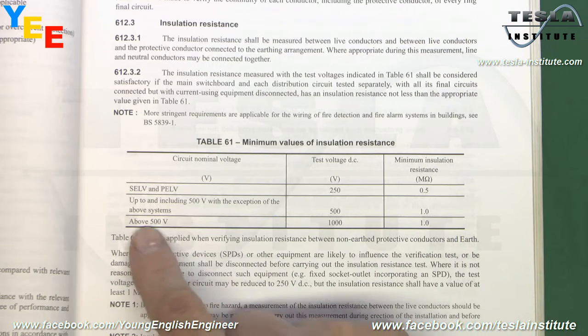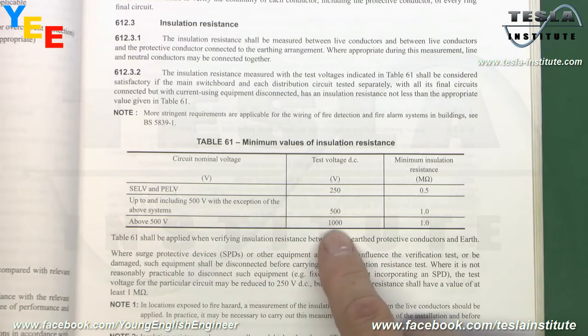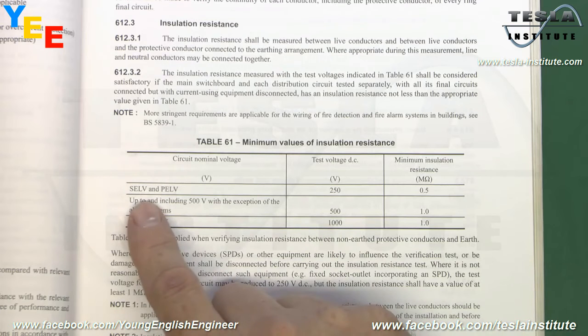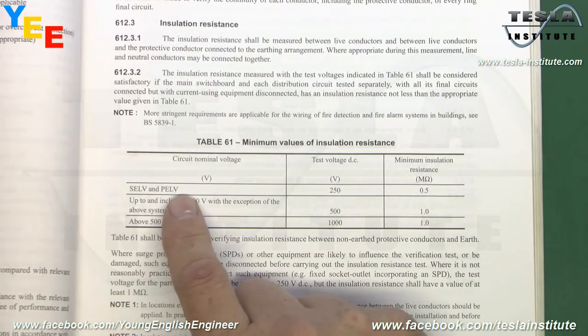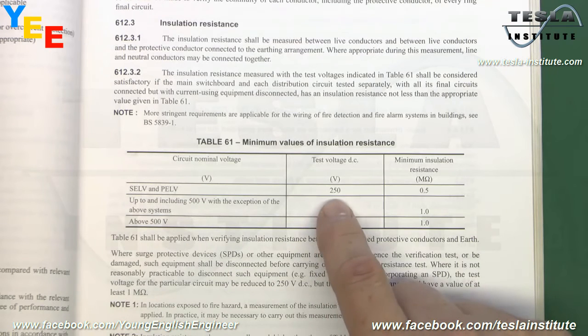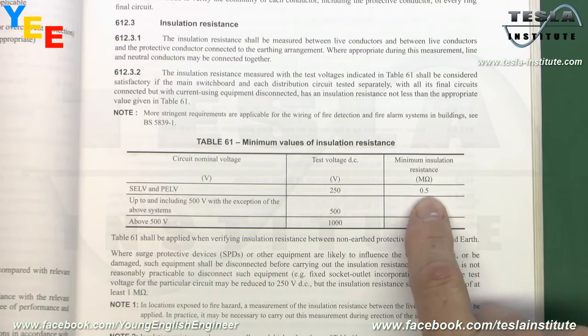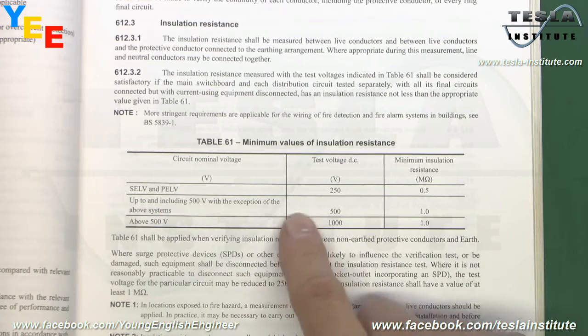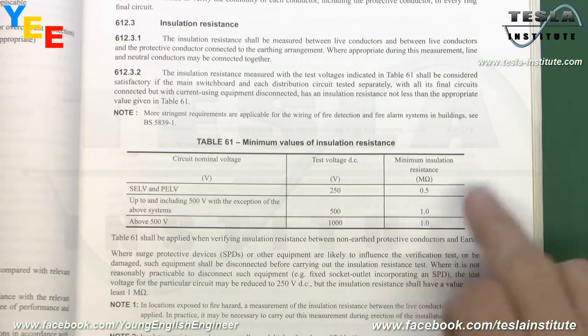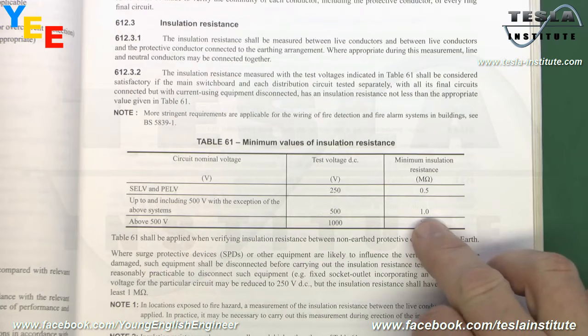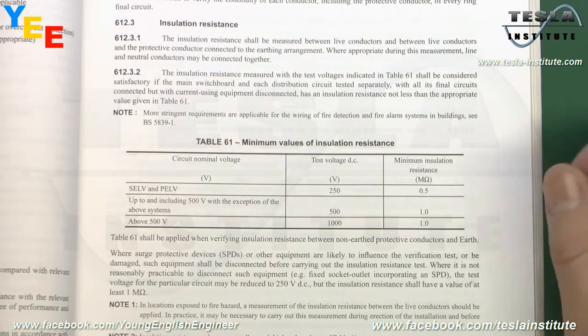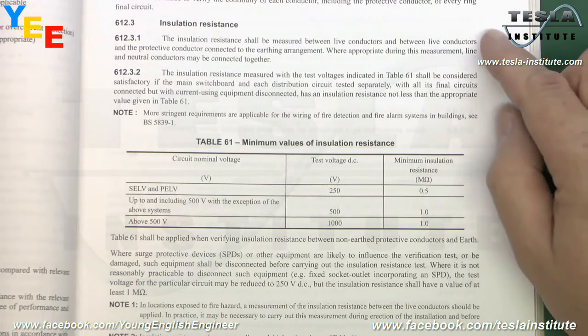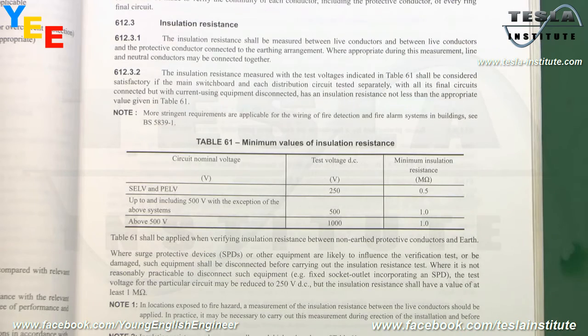The other choices here: if it's anything that normally operates at above 500 volts, then the test voltage is 1000 volts DC. And for anything less than that, as you've got your SELV and PELV circuits here, which we'll cover in another video, then the test voltage is 250 volts. The difference there is the minimum resistance acceptable is 0.5 megohms. But by far the most common is this middle one, so 500 volts test voltage and a minimum insulation resistance of 1 megohm. The rest of this section does have details on the actual procedures, but we'll go through that separately in a moment.